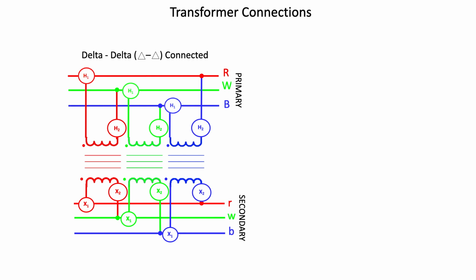The transformer having its H1 terminal connected to the R phase, or the red phase, is referred to as the red phase transformer, and likewise a transformer with the H1 terminal connected to the white phase line or bus, green in our diagram, of course, is referred to as the white phase transformer. And the transformer with its H1 terminal connected to the blue phase is referred to as the blue phase transformer.